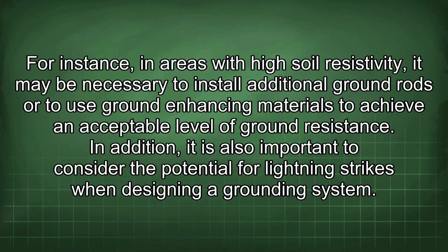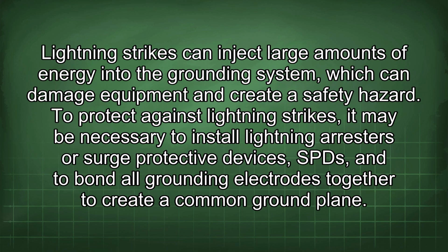In addition, it is also important to consider the potential for lightning strikes when designing a grounding system. Lightning strikes can inject large amounts of energy into the grounding system, which can damage equipment and create a safety hazard. To protect against lightning strikes, it may be necessary to install lightning arresters or surge protective devices, SPDs, and to bond all grounding electrodes together to create a common ground plane.